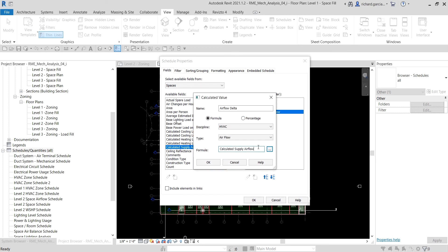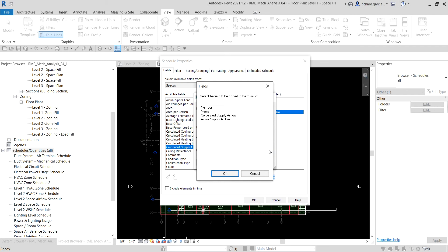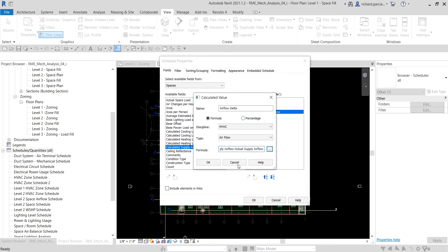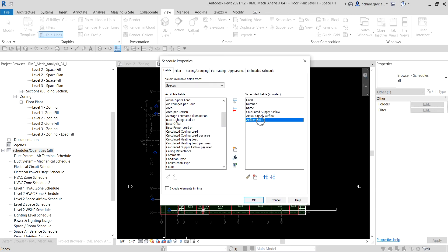Next I enter the minus sign, then click the ellipsis button again and select Actual Supply Air Flow to add it to the formula, then click OK. So the formula is: Calculated Supply Air Flow minus Actual Supply Air Flow. I select OK and the calculated parameter is now added to our schedule fields.